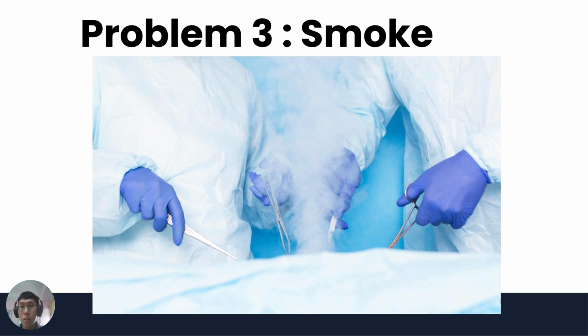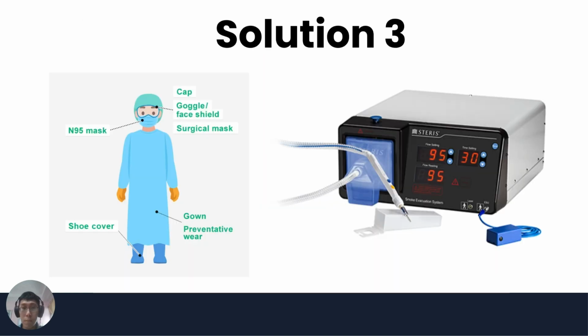The third problem is smoke. The thermal breakdown of tissue generates a smoke byproduct when the ESU is used. Various reports have verified that hazardous gases and vapors, bioaerosols, and both dead and live cellular material and viruses are found in the smoke plume. When present at high concentration, this smoke may irritate the ocular and upper respiratory tract of healthcare personnel and obscure the surgeon's view. Additionally, the smoke emits a foul smell and contains mutagenic properties.